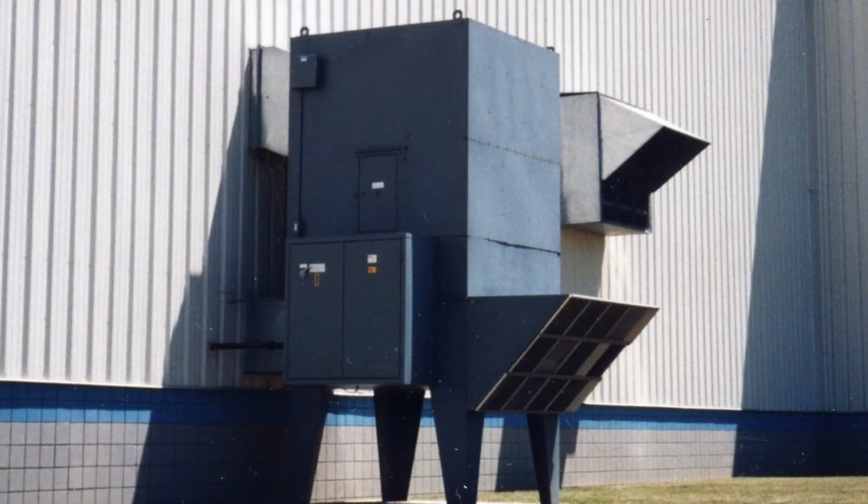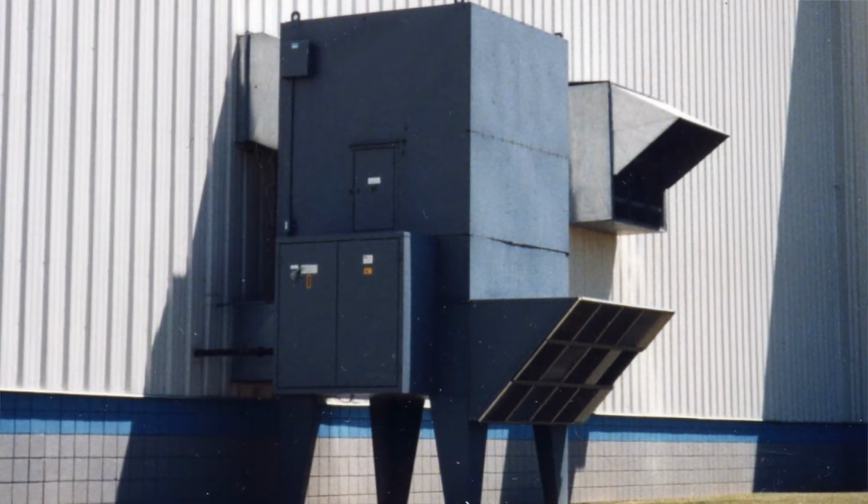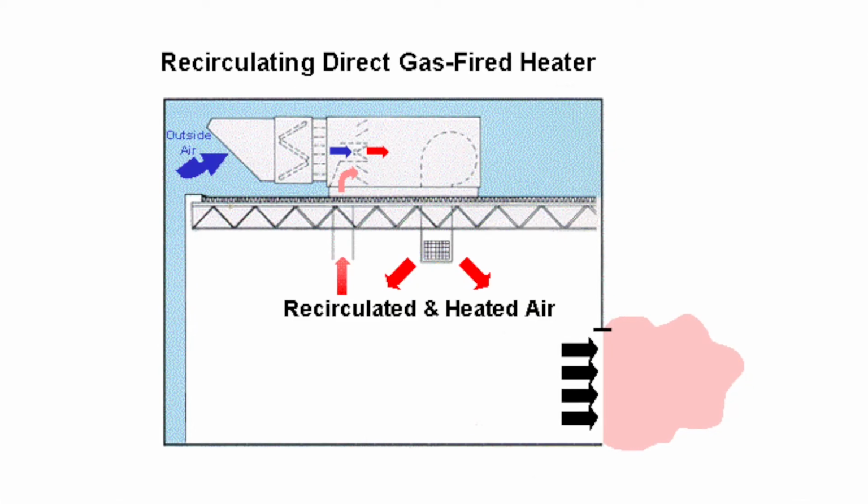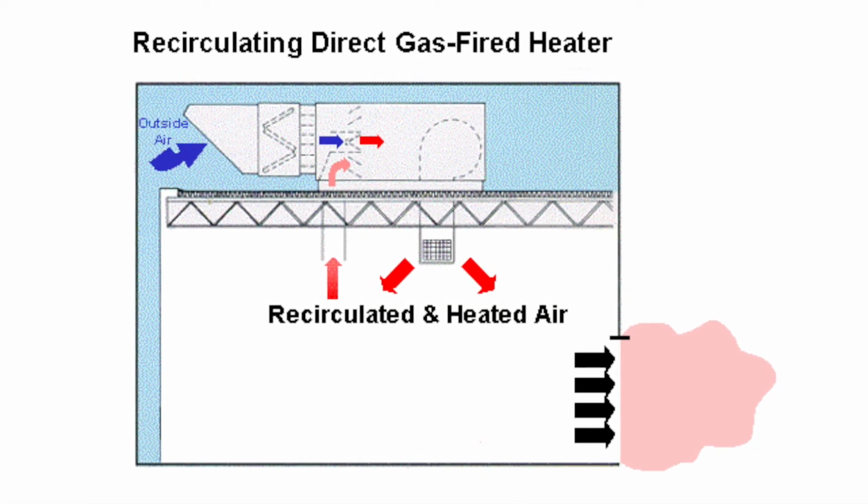Recirculation systems or 80/20 systems. There's a lot of them out in the market, and what they're utilized to do is pressurize a space. So if your contractor is specifying an 80/20 or a recirculating system in the next job that you're bidding on, ask them what happens when the dock doors open. Recirculation systems generally have a very low temperature rise, anywhere between 40, 50, 60 degrees. They also have a discharge temperature anywhere between 80 and 110 degrees, but that's a combination of the indoor air as well as the outdoor air they introduce.